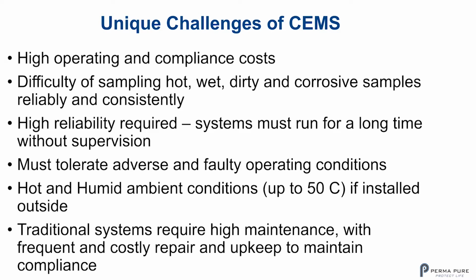So we talked about cold extractive CEMS, but some of these other methods that are newer use in situ analyzers, where you're actually analyzing the sample hot and wet at the stack level, or you're bringing down the sample hot and wet and analyzing it without conditioning it. A lot of those more advanced methods, in order to get rid of the sample conditioning, have introduced their own challenges. Some of them are unreliable. Some of them need to be cleaned on a regular basis, because the reality is it's not easy to sample hot, wet, dirty and corrosive samples.